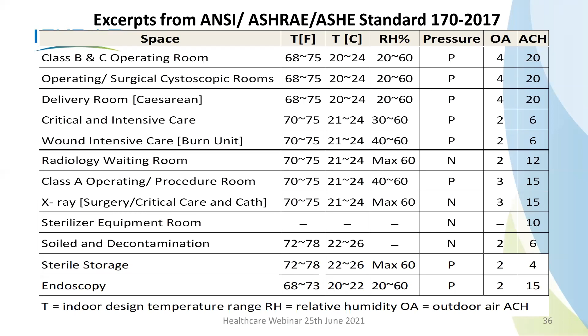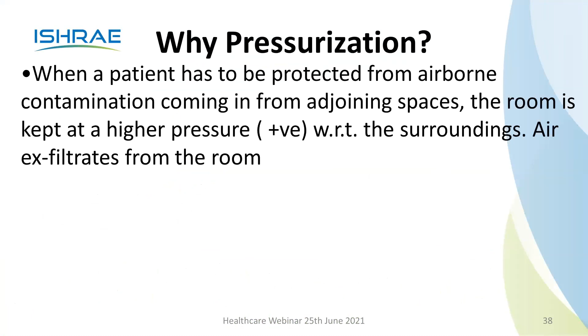Okay, so we come to the next part, that is the pressure gradient. Why pressurization? We always say that this area has to be pressurized. Why do you need pressurization? When a patient has to be protected from airborne contamination coming in from adjoining spaces, the room is kept at a higher pressure, that is positive pressure with respect to the surroundings. So air exfiltrates from the room. You can see this room. If the particular room is to be protected from outside, it is kept under positive pressure. So air will only go out, not come in.